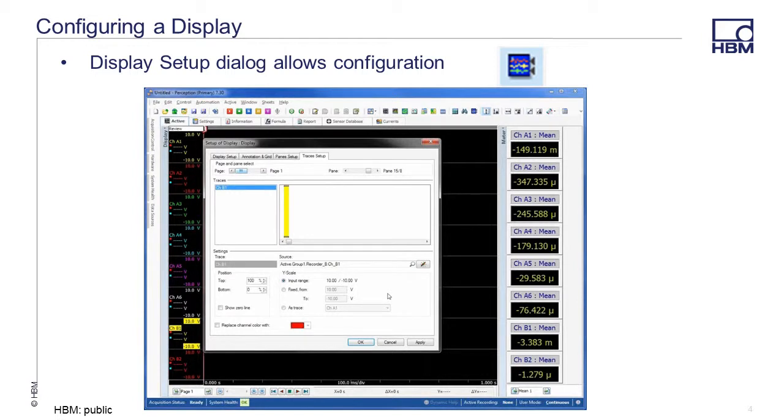The default Y scaling is the amplifier range of the channel. The user can change the default range for that trace to a different fixed range, or choose to have that trace's scale follow another trace on the same page. This can be useful if you have multiple channels measuring similar signals, maybe three phases of voltage.